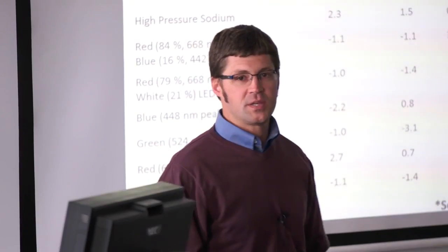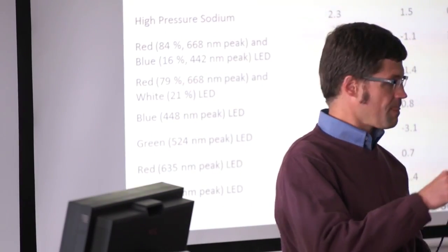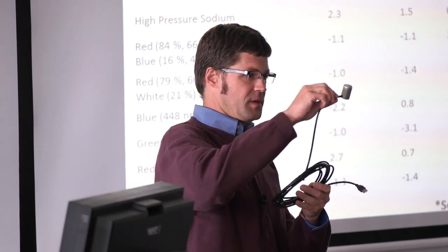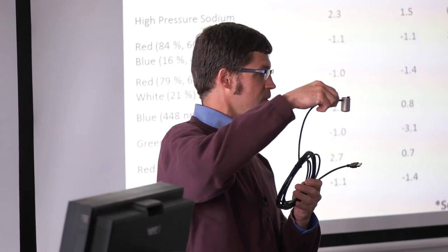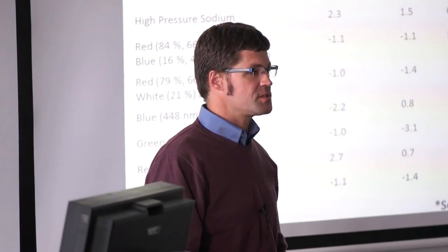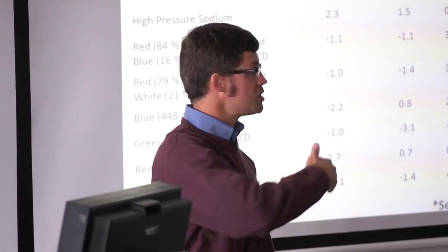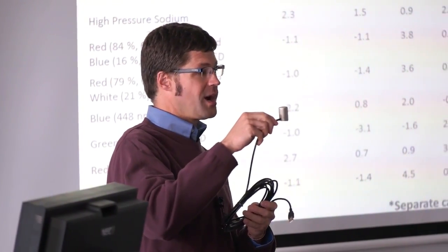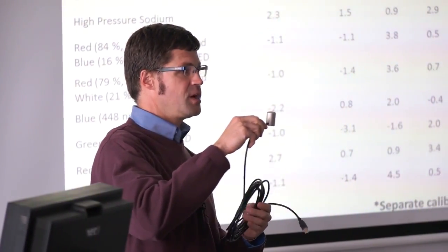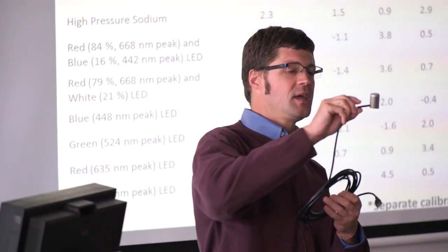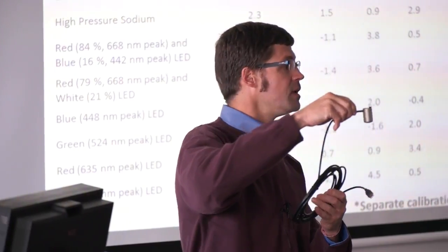And so Bruce just mentioned in the previous talk that if this were a silicon cell pyranometer, you can't invert it like that and make measurements of the surface because there's large spectral errors that are associated with doing that. And he showed a table of some of those errors. Using a quantum sensor, however, one of these PAR sensors that's designed to measure photosynthetic radiation instead of solar radiation, you can take it and invert it like this.